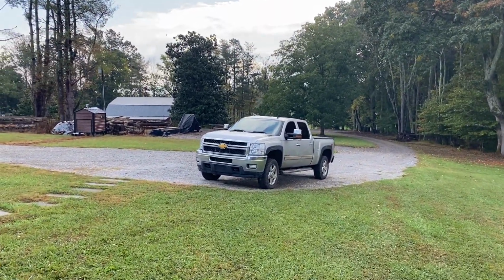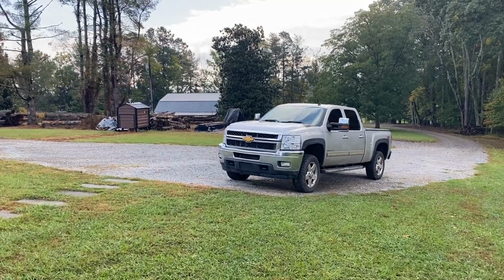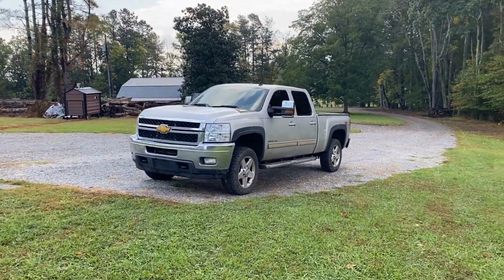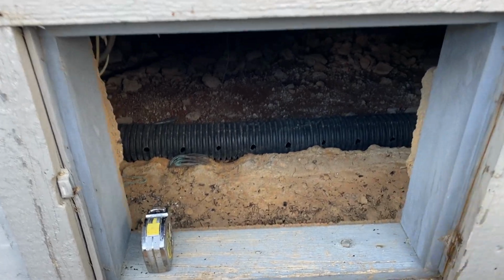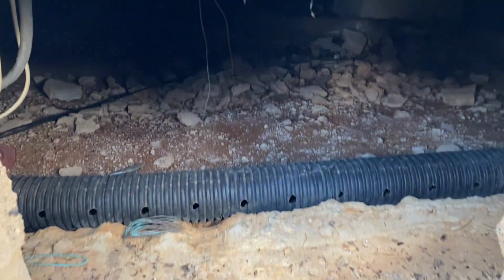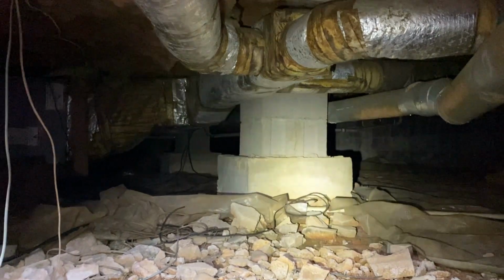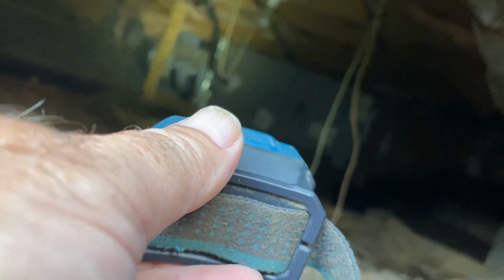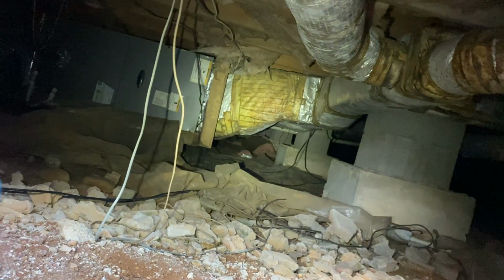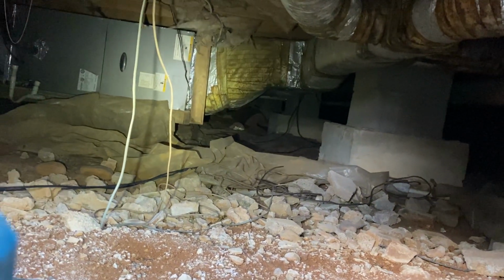But first thing I've got to do is get under there and see what I'm facing. Occasionally my memory serves me badly, and I'm pleasantly surprised. I don't know why I remembered this being so restrictive, but it isn't. I've got a light that is serviceable, I think. Got the return air right there, which means I could put it in the return air, and I've got the feed side right there, which is possible too. So I've got to measure a few things, get in there and take a look.